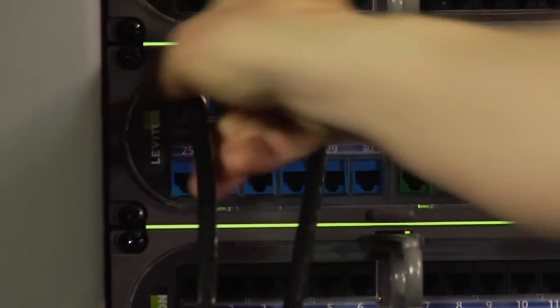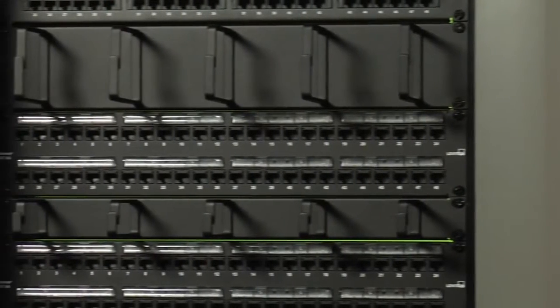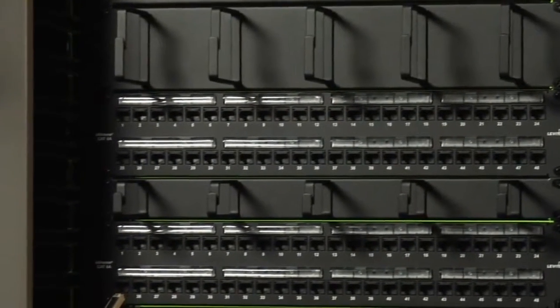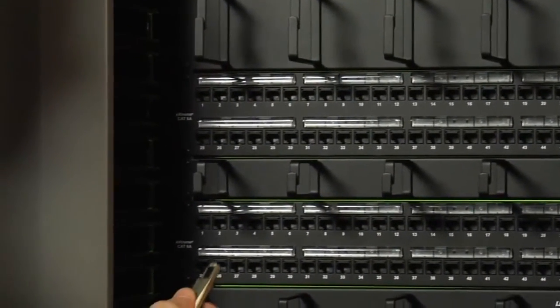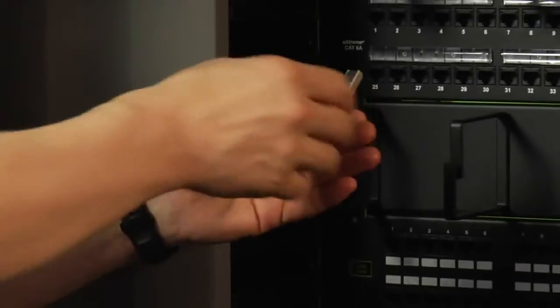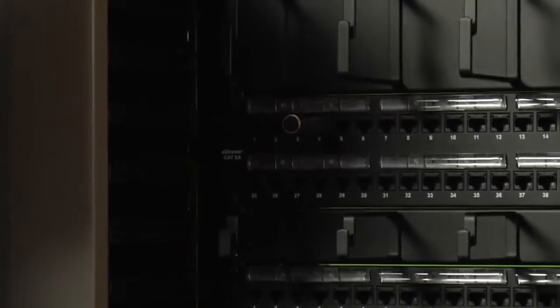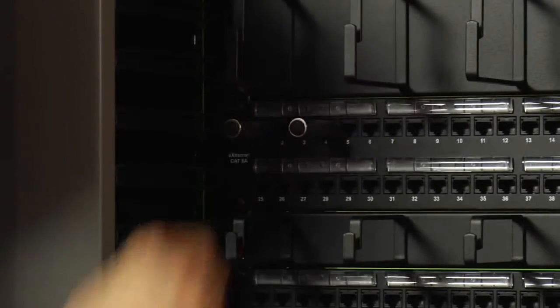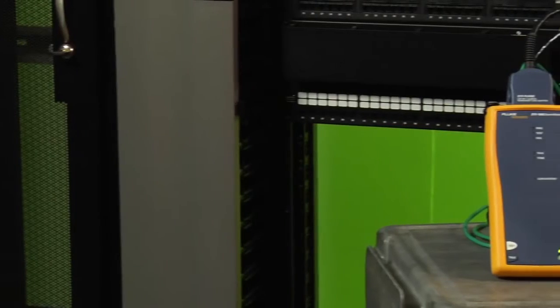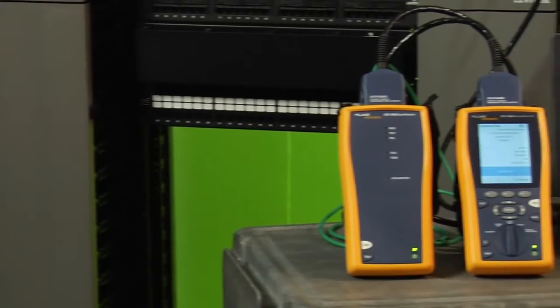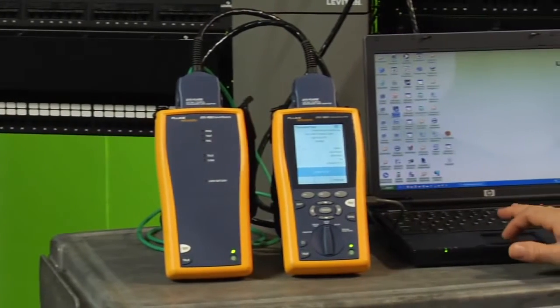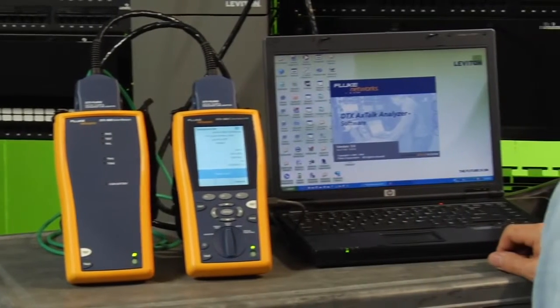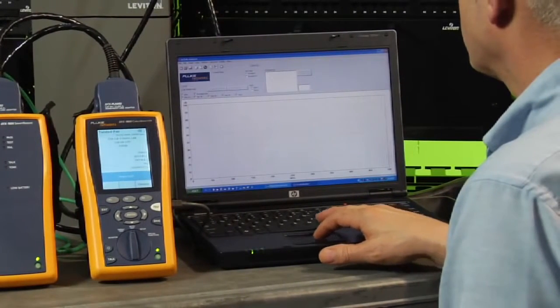You might be wondering, what about the other end of these links? They're not connected to anything. An open at the far end would create signal reflections and make the measurements invalid. So you want to plug the other ends with these terminator plugs included with your DTX alien crosstalk kit. We'll also use terminators for the open end of each disturber link. Once we've plugged into the victim link and have it terminated at the far end, you don't need to touch it. We just let the alien crosstalk analyzer software guide us through the home stretch.